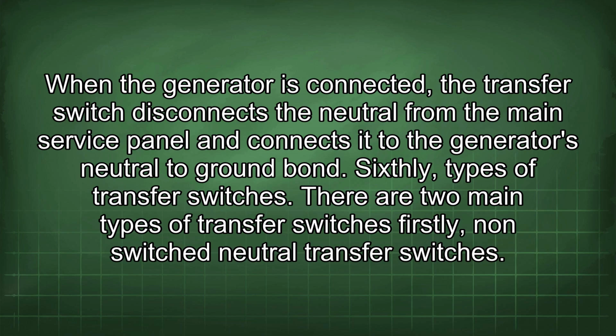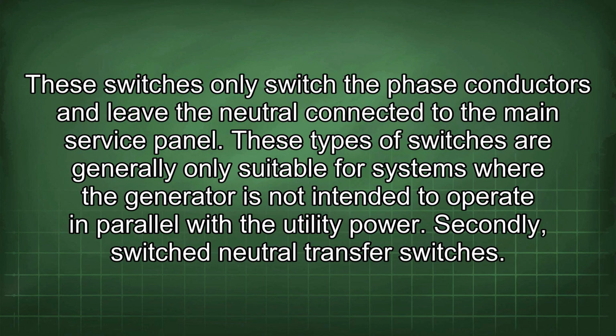Sixthly, types of transfer switches. There are two main types of transfer switches. Firstly, non-switched neutral transfer switches. These switches only switch the phase conductors and leave the neutral connected to the main service panel. These types of switches are generally only suitable for systems where the generator is not intended to operate in parallel with the utility power. Secondly, switched neutral transfer switches.